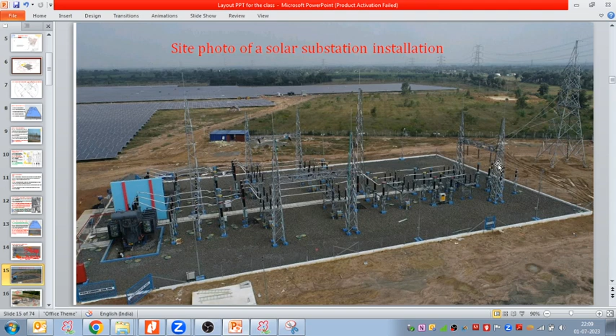This transmission line here, we can follow it here. This particular circuit, this particular equipment, is the line bay. The line bay terminates at the common bus bar, which is placed in this 90-degree direction. And then we have this transformer bay, which is again feeding the common bus bar. We know the common bus bar is a common conductor: all the circuits, the transformer circuit and the line bay circuit, connect to the common conductor.